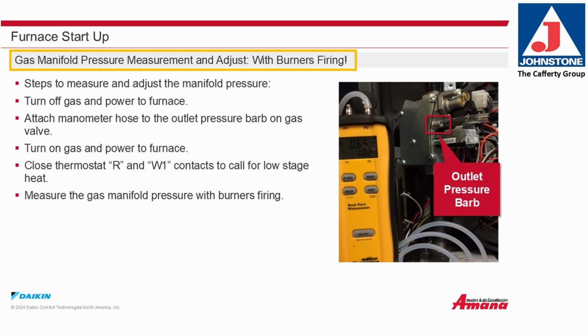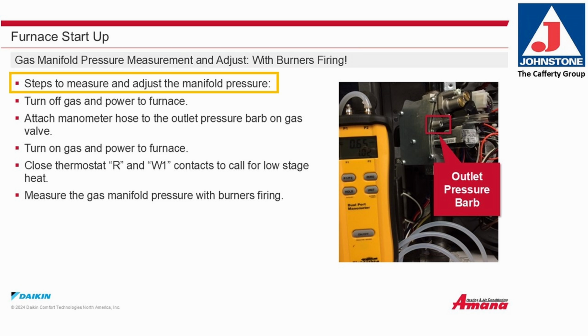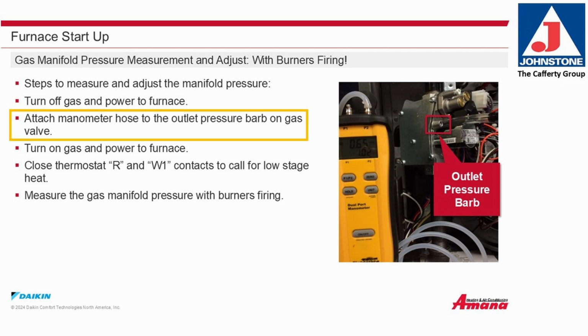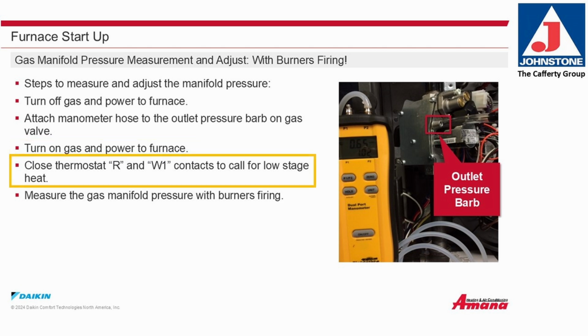Gas manifold pressure measurement and adjustment with the burners firing. Steps to measure and adjust the manifold pressure. Turn off the gas and the power to the furnace. Attach a manometer hose to the outlet pressure barb on the gas valve. Turn on the gas and power to the furnace. Close the thermostat R to W1 contacts to call for low stage heat. Measure the gas manifold pressure with burners firing.